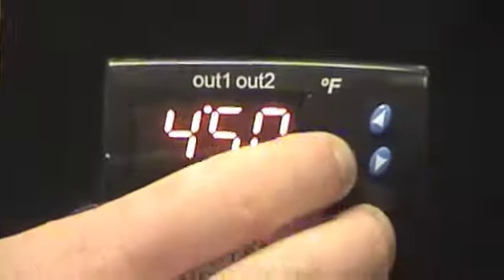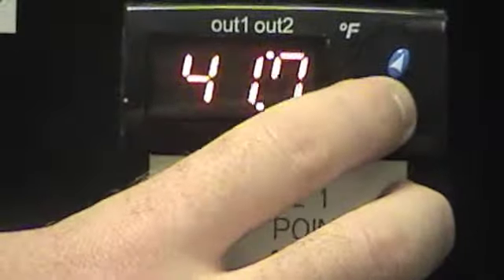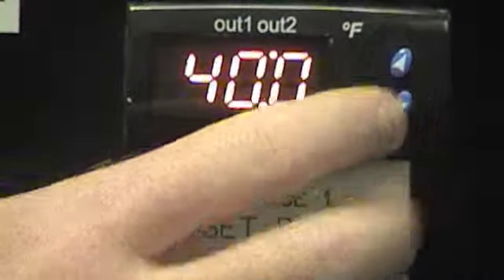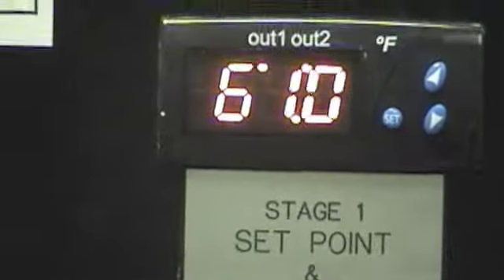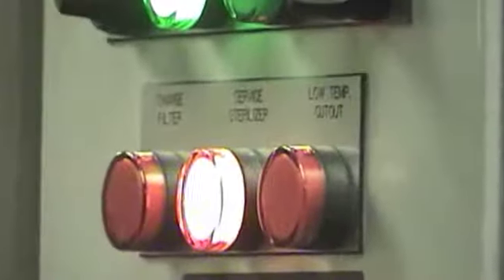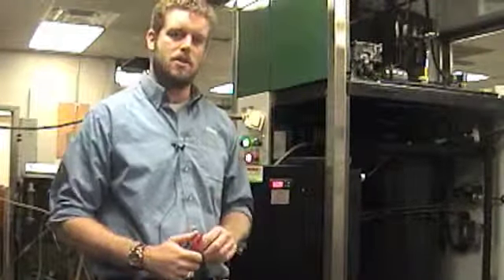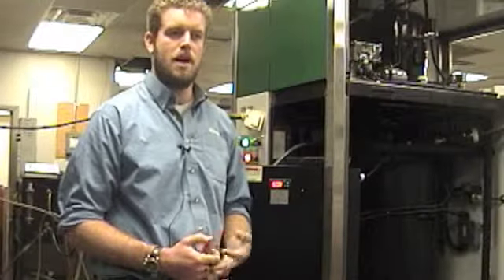And what we can do, we can drop that back down to 40. And your low temp cutout will go off. So that kind of completes starting up the chiller. We've tested the low temp cutout, tested the alarms on the unit. So the next thing we'd have to do is just button up the system and put the panels back on.